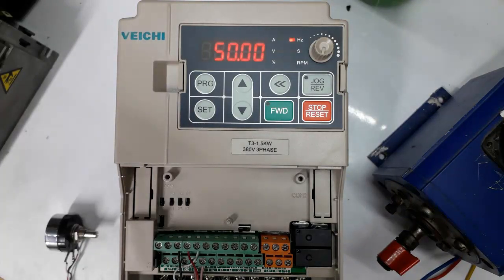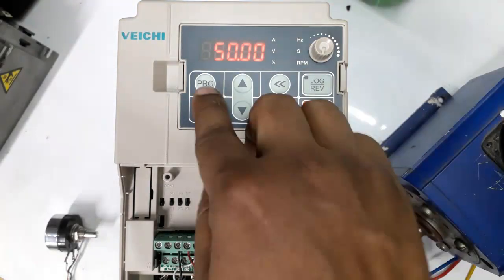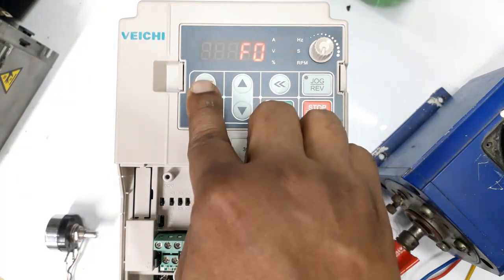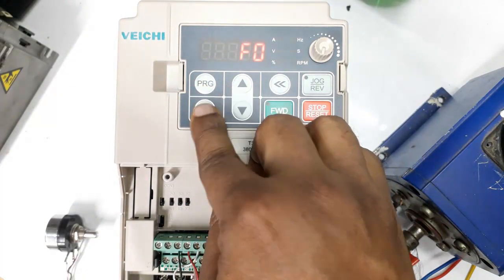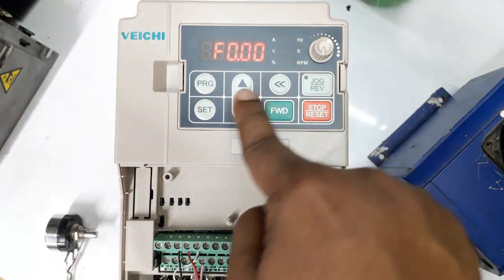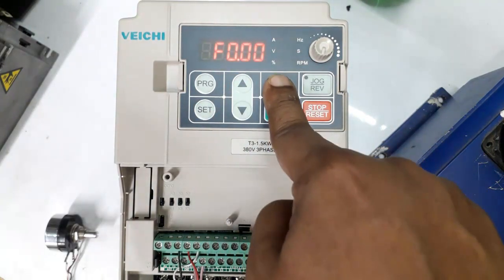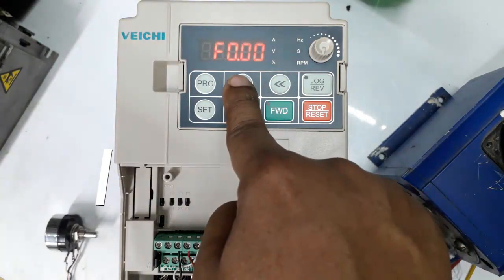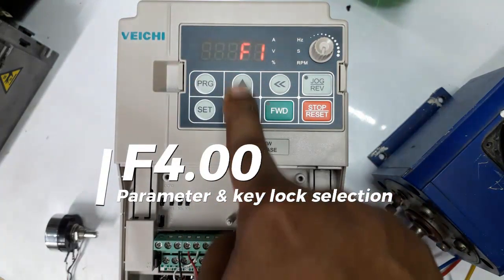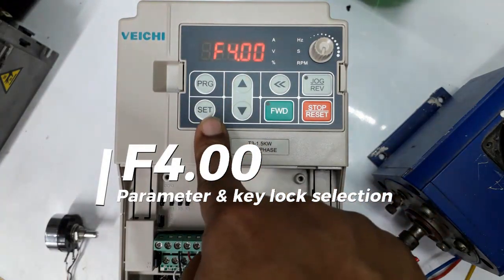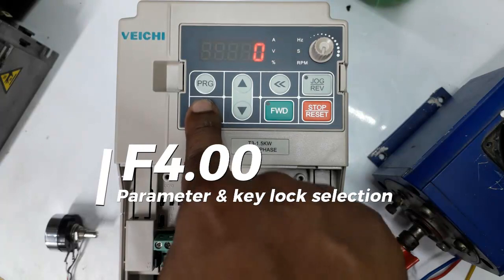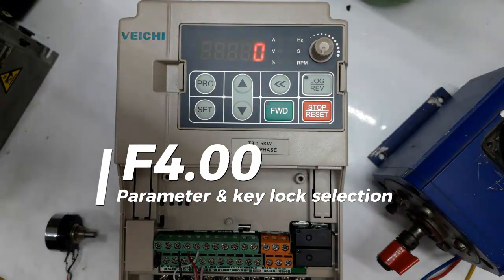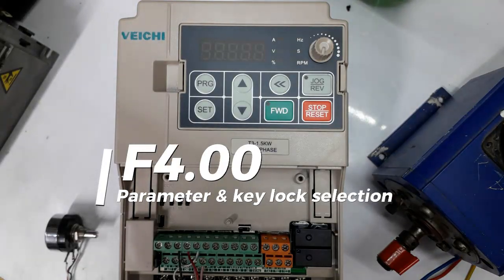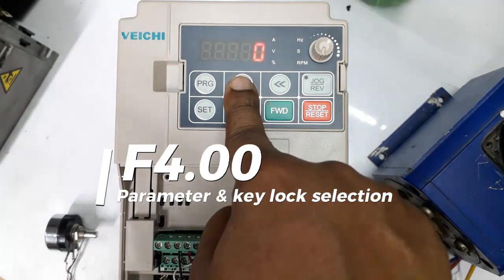Parameter lock and copying in the VCSE 200 drive. This drive's parameter locking parameter is F4.00. In the group F4, parameter number 00, that means F4.00, is the parameter lock or keyboard lock parameter. Here it is showing 0, that means the keyboard is unlocked.